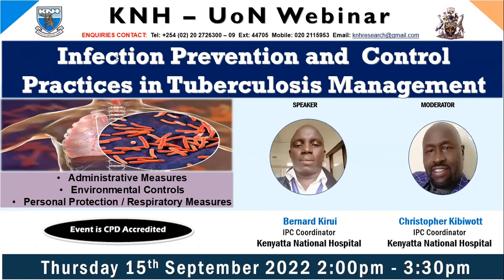Okay, usually the decontamination protocol depends on what you are trying to decontaminate. If it is an instrument you have used in theater, we usually start with an enzymatic cleaner, called enzymatic detergent. In most cases, it's called Endozime. That one removes all the bioburden and makes sure that any droplets of blood, pus, small tissues are wiped from the instrument. Then we insert in a decontaminant. Remember, the first process takes place in the ward. The second process, which is now beginning the decontamination process using the jik, sodium hypochlorite, and any other available material, starts from CSSD and ends there.